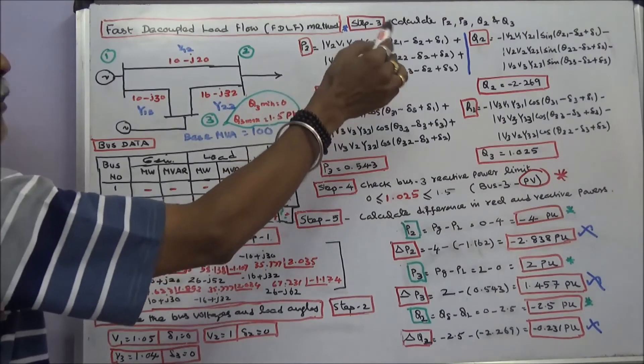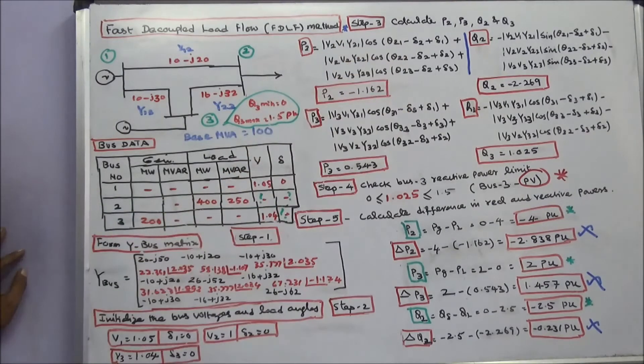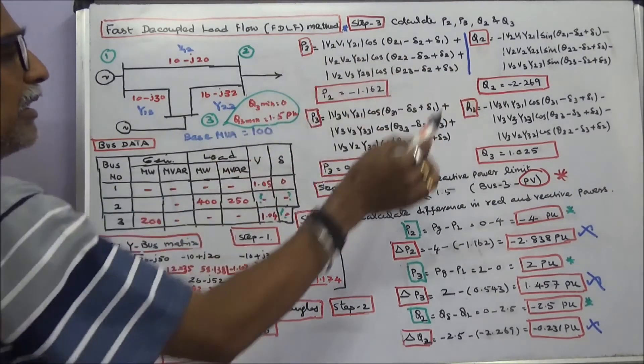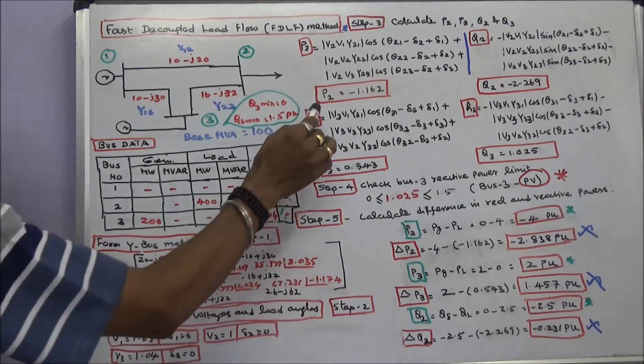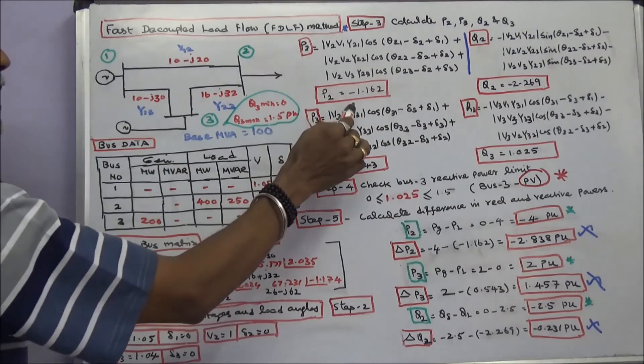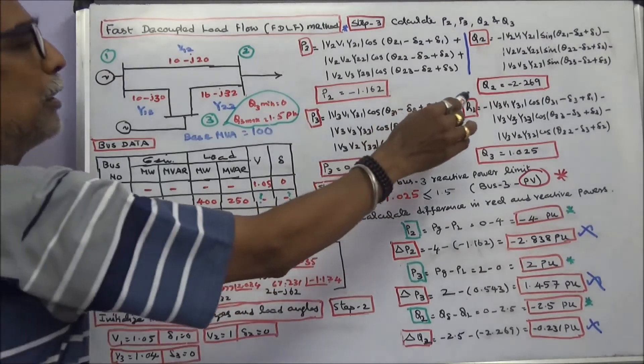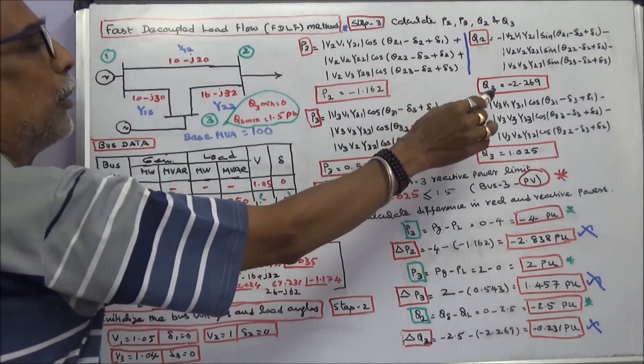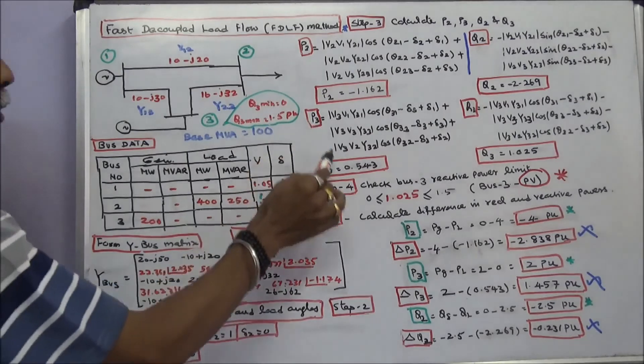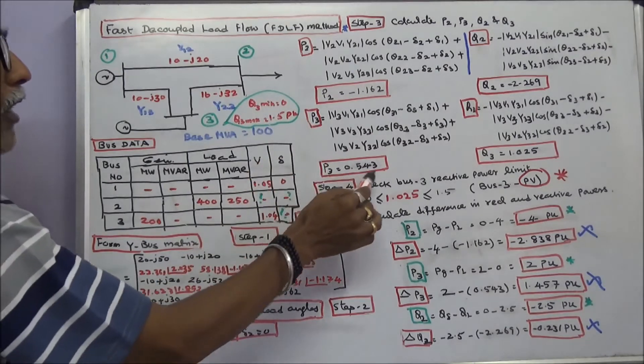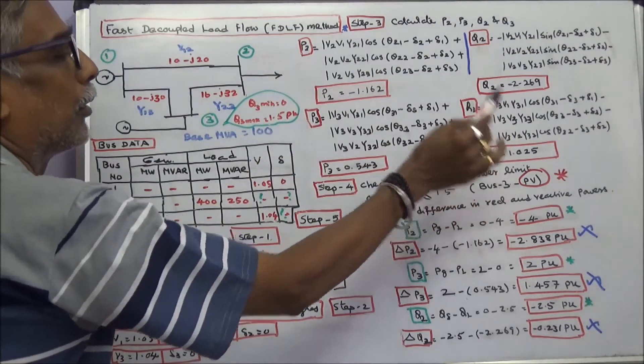Step 3: Calculate P2, P3, Q2, and Q3 using the load flow equations. P2 equals minus 1.162, Q2 equals minus 2.269, P3 equals 0.543, and Q3 equals 1.025.